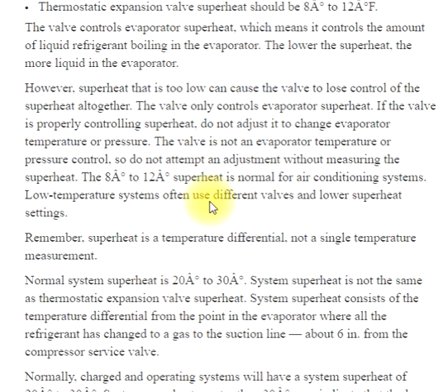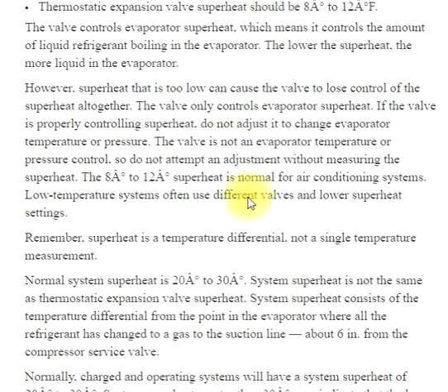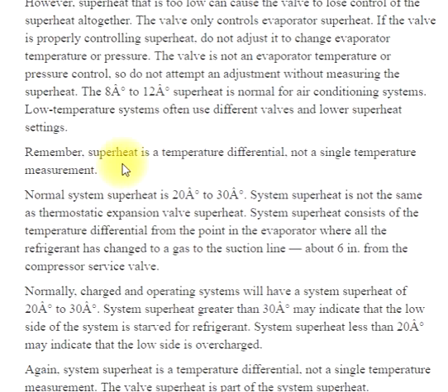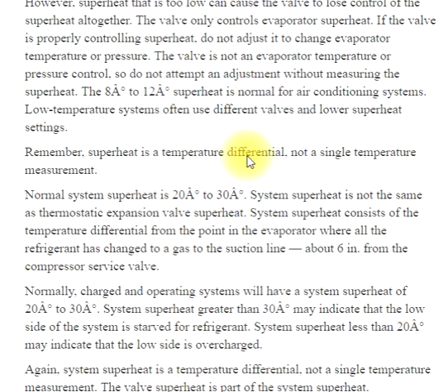The 8° to 12° superheat is normal for air conditioning systems. Low temperature systems often use different valves and lower superheat settings. Remember, superheat is a temperature differential, not a single temperature measurement.